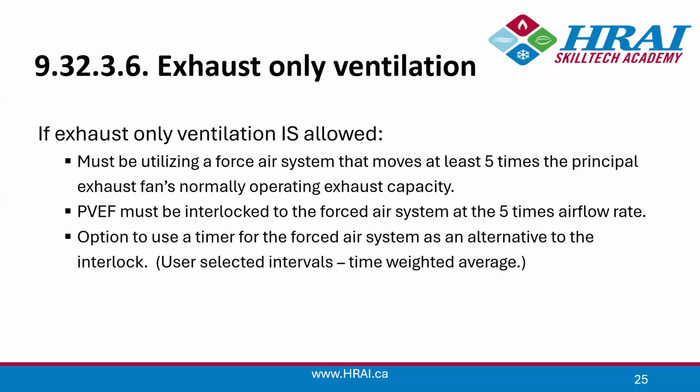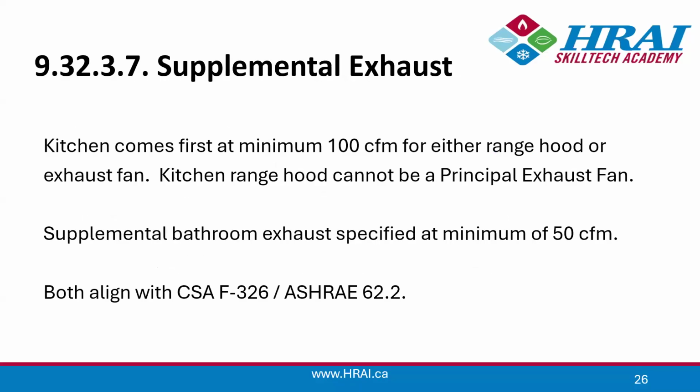So far, so good. The next piece of our heating season ventilation system is supplemental exhaust. So our kitchen comes first, and that's specifically stated as 100 CFM for either a range hood or a kitchen exhaust fan. The kitchen range hood cannot be the principal exhaust fan, and the main reason for that is on the next slide. So I won't give it up just yet.